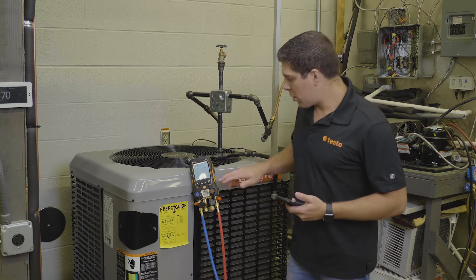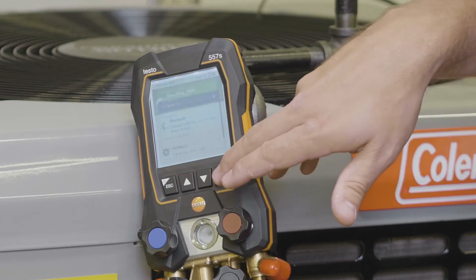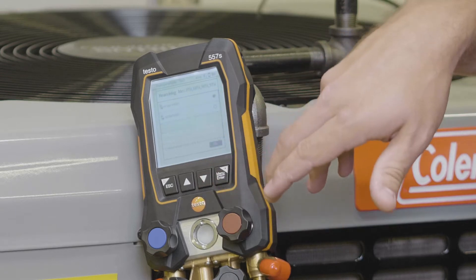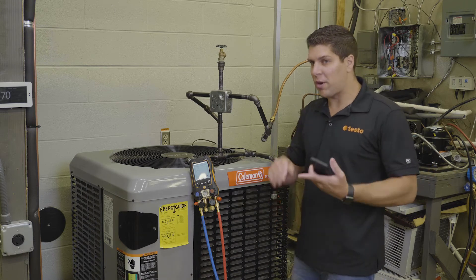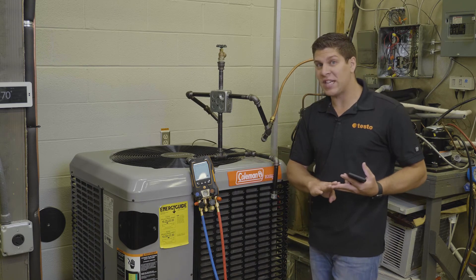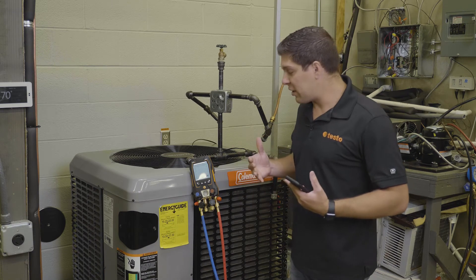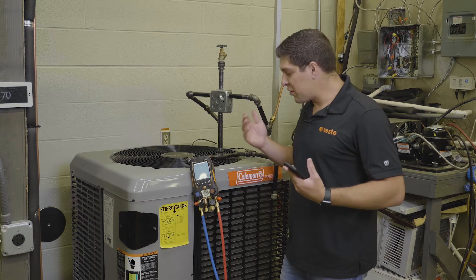So what we're going to do is go back into our menu, hit measuring modes, and go down to the pressure leak test. The pressure leak test does allow for temperature compensation, so you can use smart probes — whether you have a 905i, a 115i, or the new 915i thermocouple type K smart probe — you have the ability to use those to get your temperature compensation. For now I'm using a 115i.